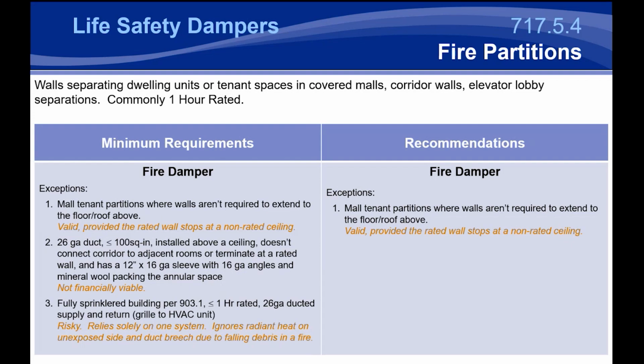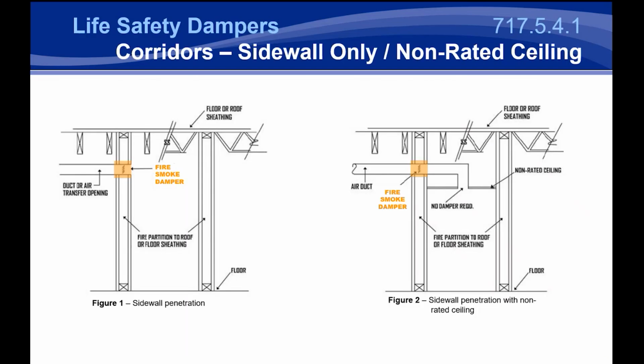That fully sprinklered exception does come up again for the fire partitions as well as the fire barriers. It's pretty much the same risk that I had mentioned before, so I won't go through that again. Now, getting into corridors, as a damper manufacturer, we kind of lump these into three different categories. It has to do with the rated ceiling for those corridors. So these corridors are going to have a rated wall typically for all their applications. But there are a lot of corridors that do not have a rated ceiling. So there's really no requirement to protect the ceiling. It's just a finished ceiling that has no rating.